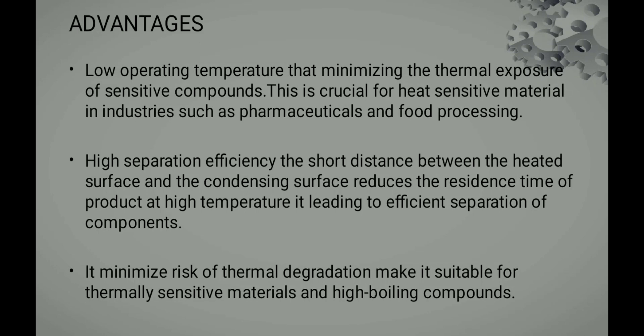Let us see a few advantages of the short path evaporator. First, low operating temperature minimizes the thermal exposure of sensitive components. This is crucial for heat sensitive materials in industries such as pharmaceutical and food processing. Second, high separation efficiency — the short distance between the heated surface and the condensing surface reduces the residence time of the product at high temperature, leading to efficient separation of components and minimizing the risk of thermal degradation, making it suitable for thermally sensitive materials and high boiling components.